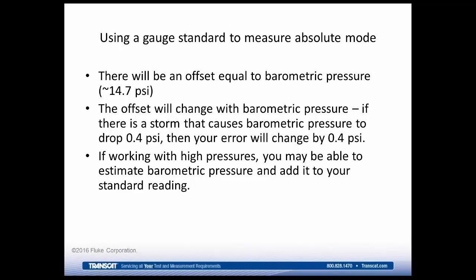If you're working with high pressures, so if you're at 10,000, 20,000 psi or higher, these problems may not be an issue for you. You can just estimate what the barometric pressure is and add it to your standard reading. So if your device under test is reading 14.7 at atmosphere and your standard is reading 0, you just add 14.7 to your standard as an estimate of barometric pressure, and assume it's not going to change enough to matter at 10,000 or 20,000 psi. There, you may only be looking at the pressure plus or minus a psi, or plus or minus 2 psi, or plus or minus 10 psi. If that's the case, then if your barometric pressure changes by 0.1 psi, it doesn't really affect your overall measurement.